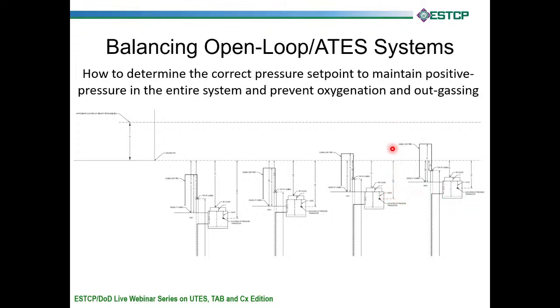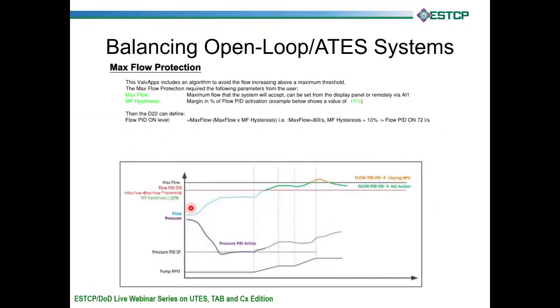Now we can calculate the height of this, and the height of this one, and the height of this one. So essentially each one of these wells, the injection valve controller, has to have a different pressure set point in order to make the valves all control to the same set point so that they get the same amount of flow rate. The other set point that we have is max flow. So we tell our controller, hey, we don't want you to go over 500 gallons a minute. If you go over 500 gallons a minute, start closing down.